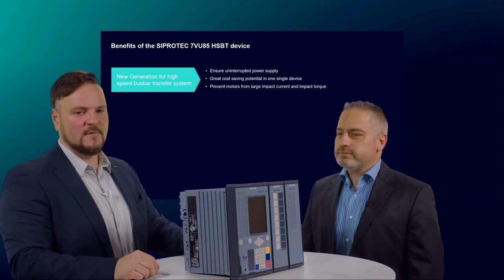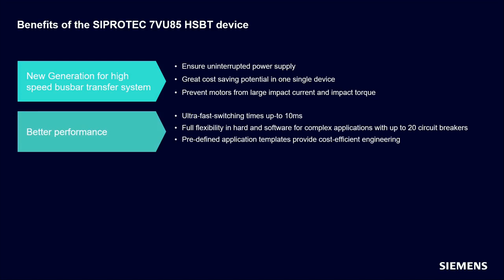Okay, the benefits of the SIPROTEC 5 7VU85 HSBT is that we ensure an uninterrupted power supply. We have a great cost-saving potential in one single device. We prevent motors from large impact current and impact torque. Then we have a better performance. That means we have the new ultra-fast switching times up to 10 milliseconds with the fast mode. We have the full flexibility with hardware and software. That means we support up to 20 circuit breakers, which is very unique in that area. We have predefined application templates, which just make it easier to start your engineering and to save some time.